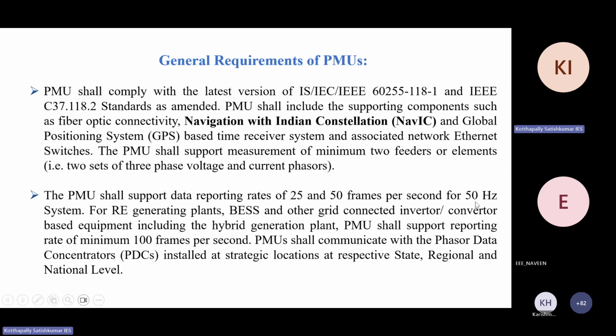Now we have given other requirements also. We told them PMUs shall support data reporting rates of 25 to 50 frames per second, because the more frames you get, the more accurate the data. So basically PMUs don't have any problems. The problem we are seeing is basically the fiber network connectivity. So in phase 2, we advised Power Grid that even if a substation doesn't have a fiber optic network, they should commission the fiber optic cable and then place the PMUs. Now it is mandated. Another thing is that all the upcoming substations are mandated to have PMUs. So the under-construction and future substations will have compulsory PMUs, and they will install PMUs in the substation.